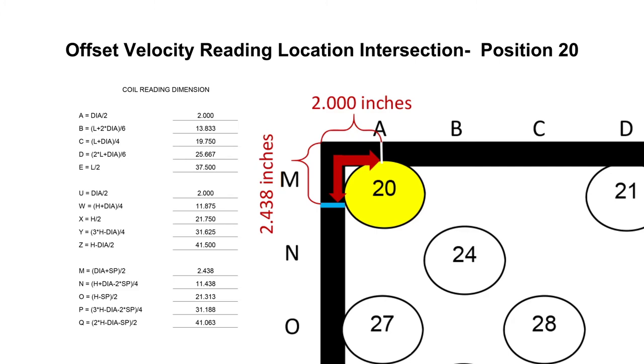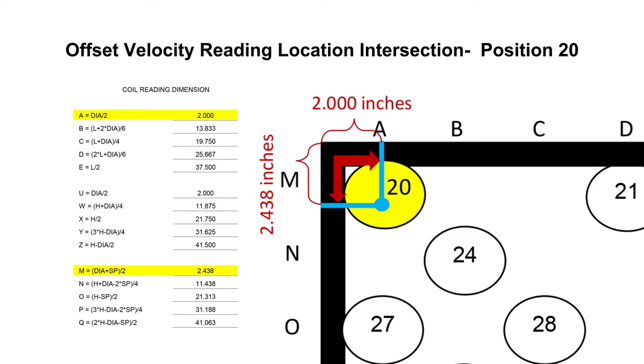The offset velocity reading location for position 20 is at the intersection of A and M. The value for A equals 2 inches and the value for M equals 2.438 inches. A measurement and marking for A is 2 inches from the left towards the center, and for M, 2.438 inches from the top towards the bottom. Therefore, the position 20 offset velocity reading location is at the intersection of A, 2 inches from the left to center, and M, 2.438 inches from top to bottom.